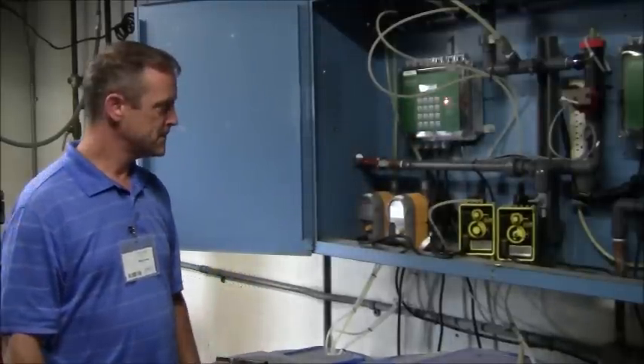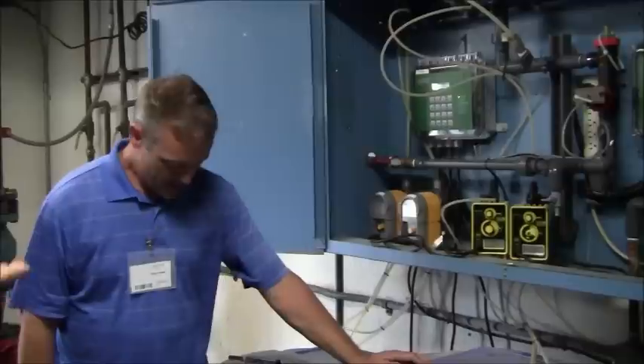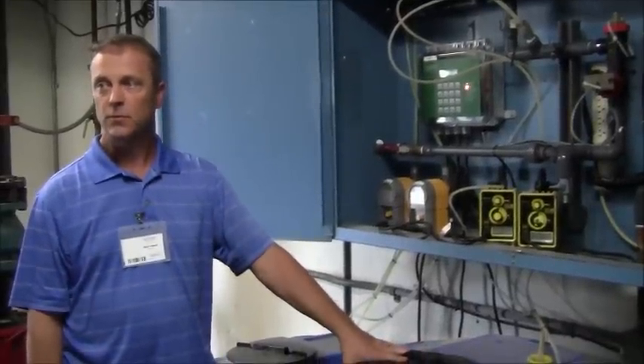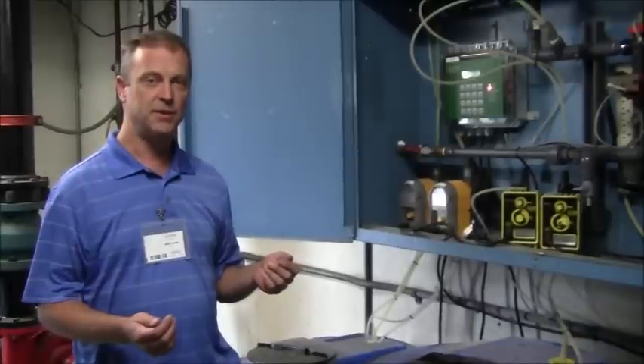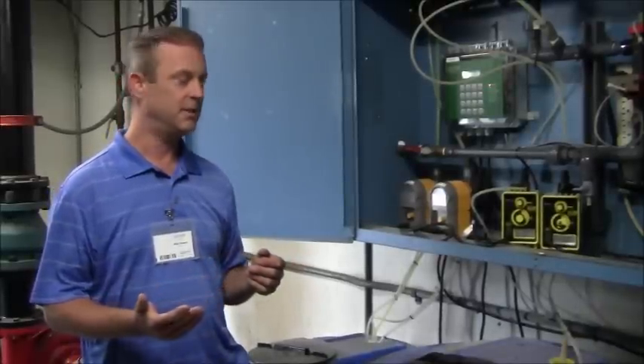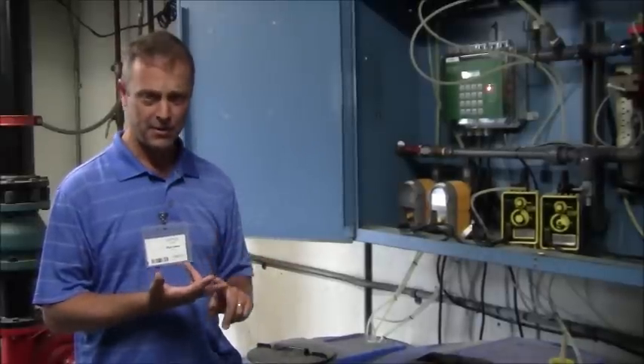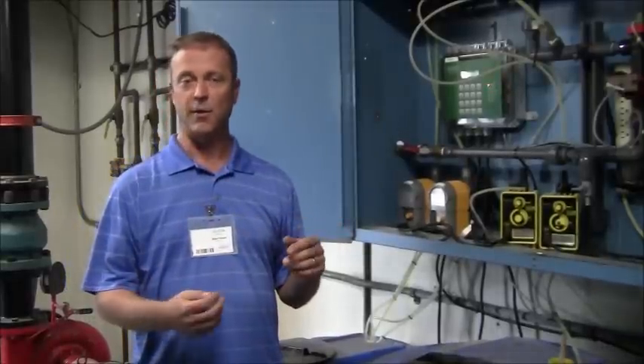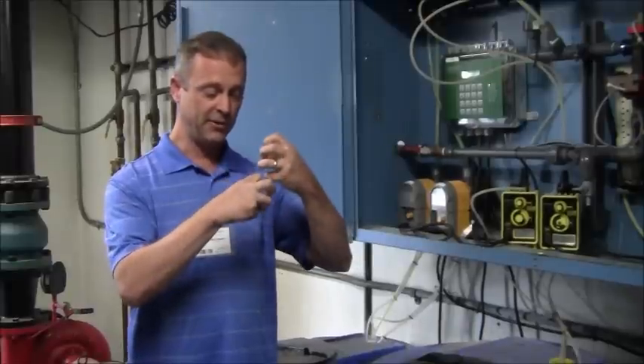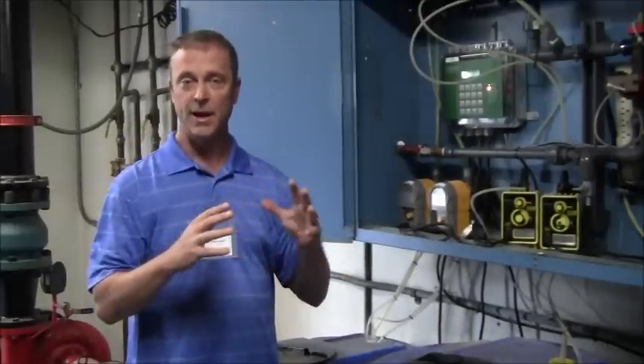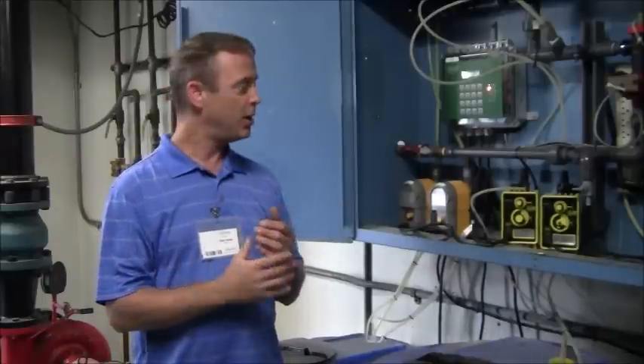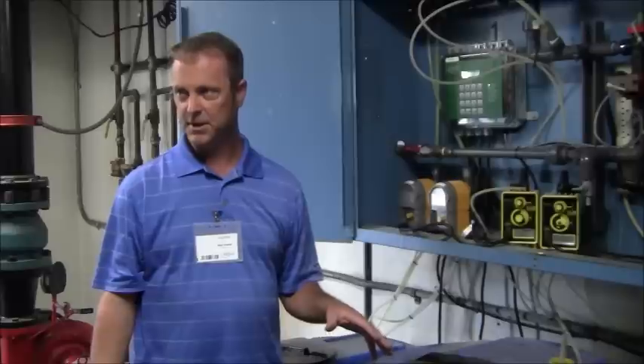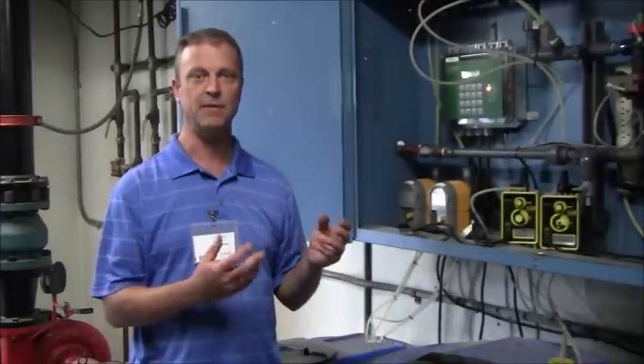What does the inhibitor chemical actually do to the water? Why that particular chemical as opposed to something else? Okay, what the cooling tower inhibitor is designed to do is tackle all the impurities in the water that we were mentioning previously. So you're going to have a lot of hardness, calcium and alkalinity, the dirt, the turbidity in the cooling tower. And the inhibitor is basically a crystal modifier. It prevents these two, calcium and alkalinity, from bonding together to form scale. It tweaks them and then they can't connect together. And that's done basically with a polymer. We trace the product with a molybdenum product so that we can see how much treatment we have in the system.